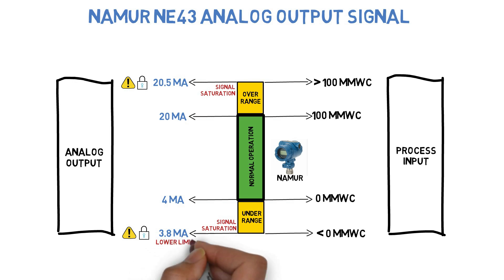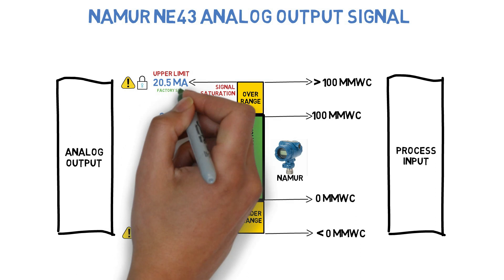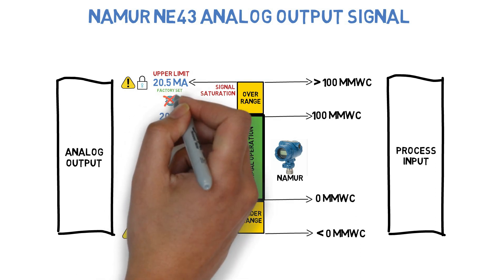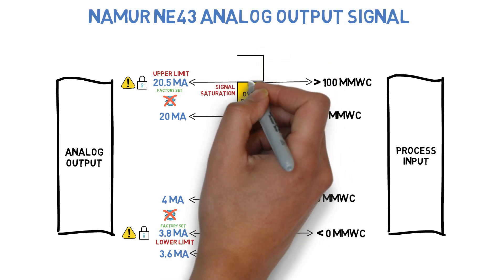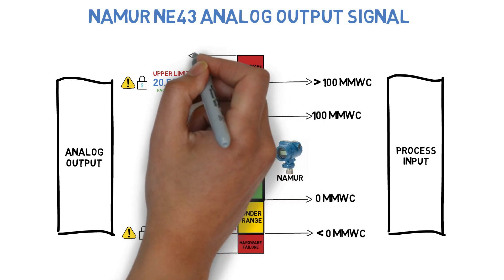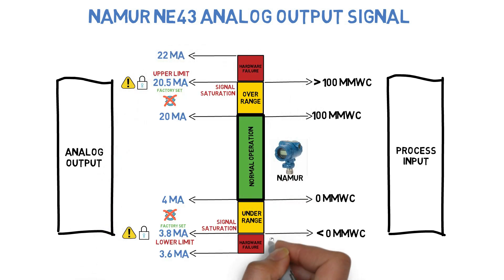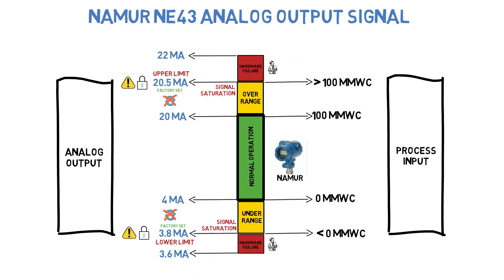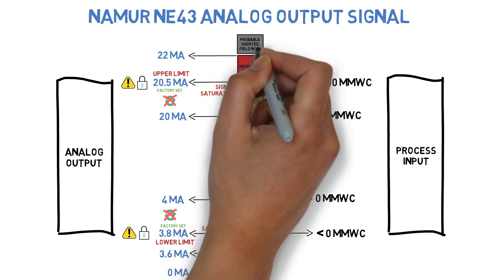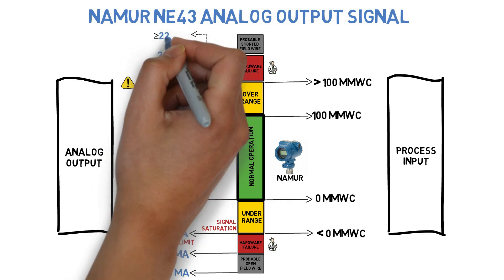The analog output lower limit and upper limit are factory set, and cannot be changed. On hardware failure, the transmitter output changes to either 3.6 or 22 mA. This high-low selection is user-selectable through transmitter configuration. If the field wire is open, the transmitter output changes between 3.6 and 0 mA. If the field wire is short-circuited, the transmitter output shall be greater than or equal to 22 mA.